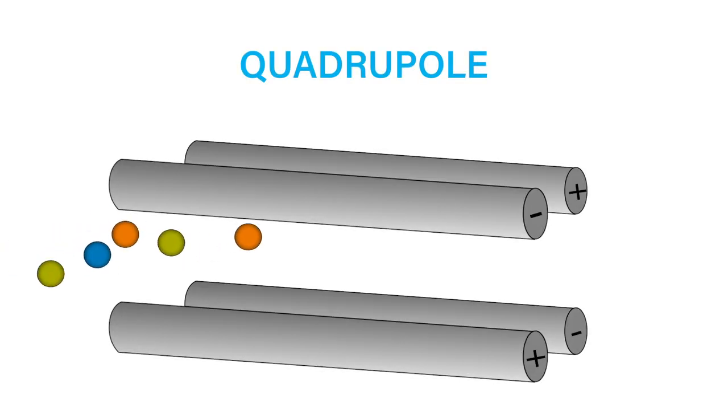Let's take a closer look at how a quadrupole works. Within the quadrupole assembly, a fluctuating field is created by applying RF and DC voltages to the quadrupole rods. Opposite rods have the same voltages applied.